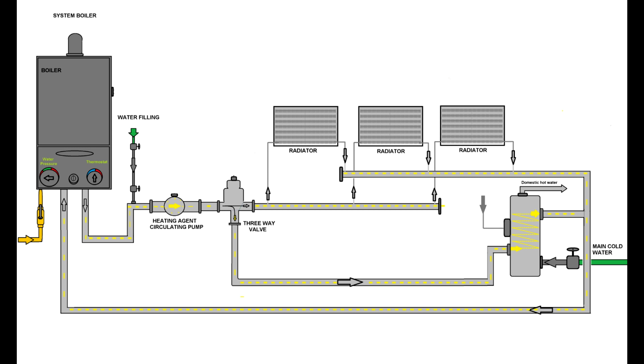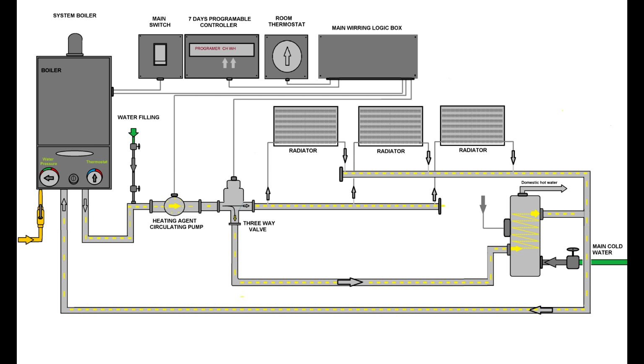When all the plumbing is done, you fix the electrical system. That should be done by an electrician. Then you turn on the filling line and you fill the system with water, because if you start the system without water, the boiler will go into fault mode. So when the system is full, you have to turn off both valves on the filling line for safety. Make sure you're not exceeding the pressure in the system.